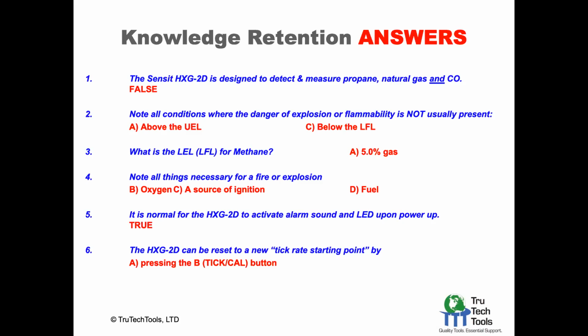And then yes, the HXG-2D does go through an activation sequence where things are going to go off on you. So it's true, you're going to hear some normal startup sequences, which will indicate the alarm, but only briefly. And then you reset the new tick rate. The big clue here is the tick cal button is what you use to reset the tick rate. So it's pressing the B button, which says tick or cal on it. That gets you a new threshold on your gas detection, your inspection mode.